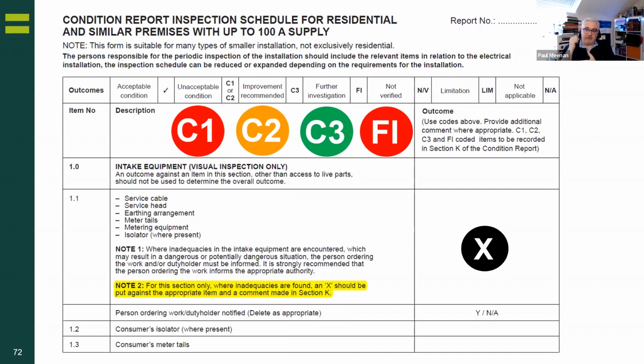So my recommendation is ring 105, get a fault report number. And also, me personally, this is my personal opinion now, if I went to a DNO head and it was melting, or there was a phenolic issue, or there was a major earthing problem, I wouldn't just leave it. I would do everything within my power that's reasonably practicable. Yes, note it down. Yes, ring 105, but make sure that customer knows they've got to get something done. And I would also check back in as well, to be honest with you, to make sure it's done, because I have an inherent fear that this is to help with the workloads of the DNOs, because this equipment is getting older and older and older. So just be mindful when it comes to working around this equipment.